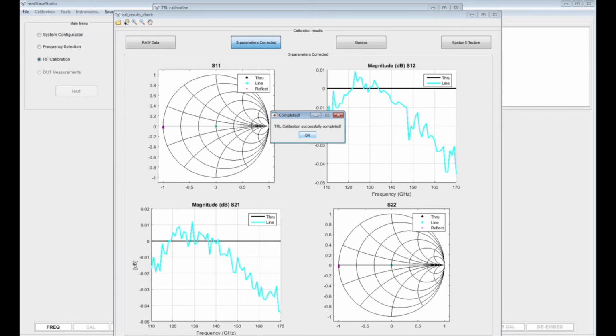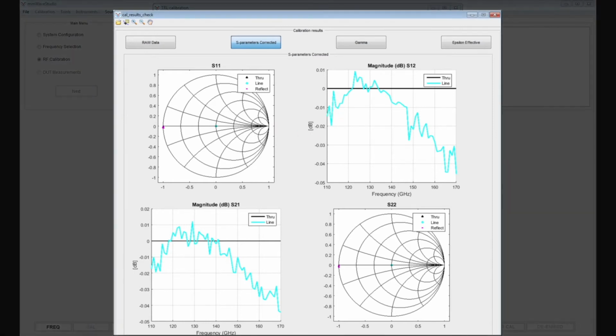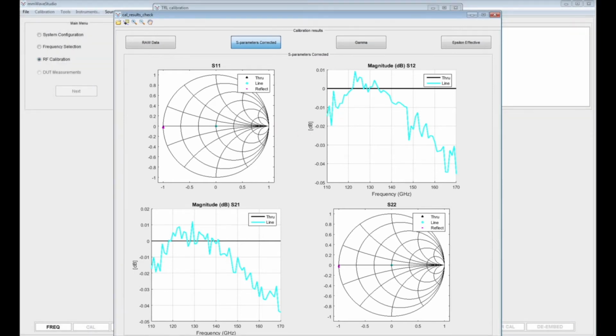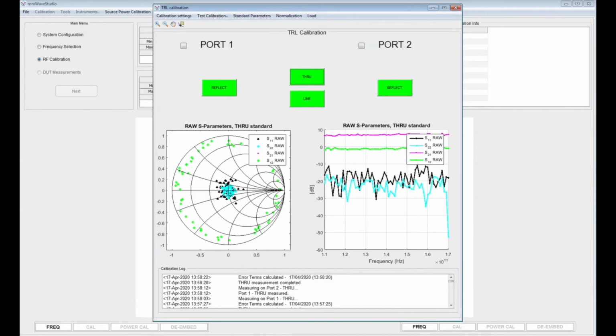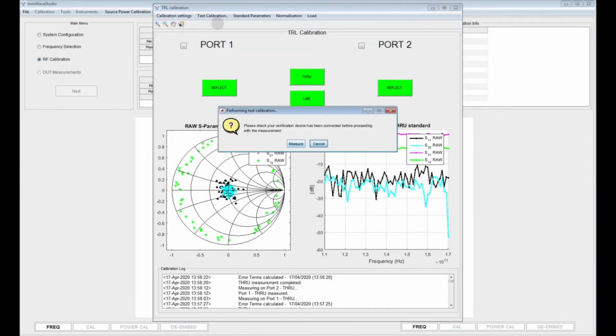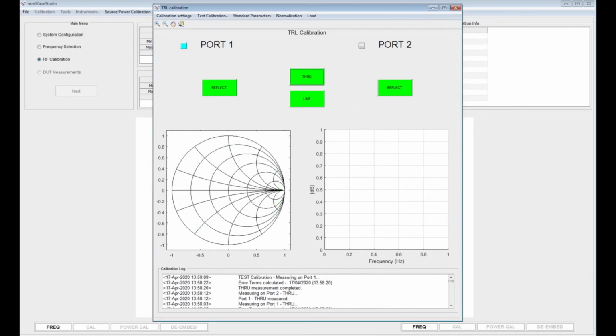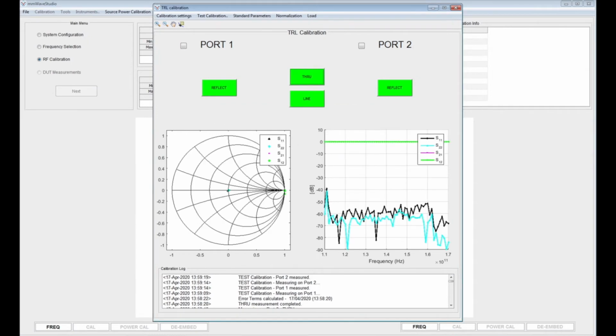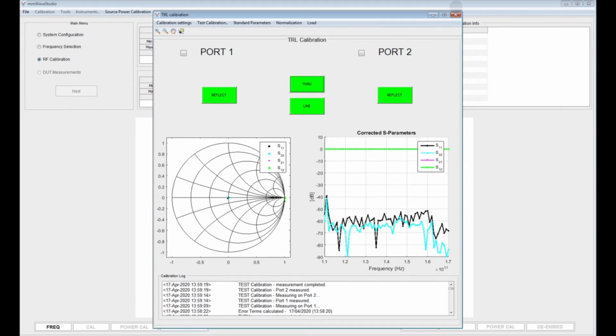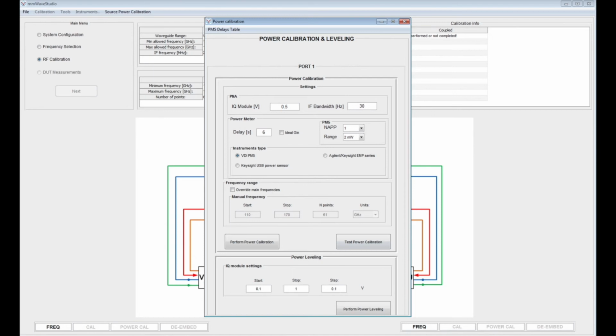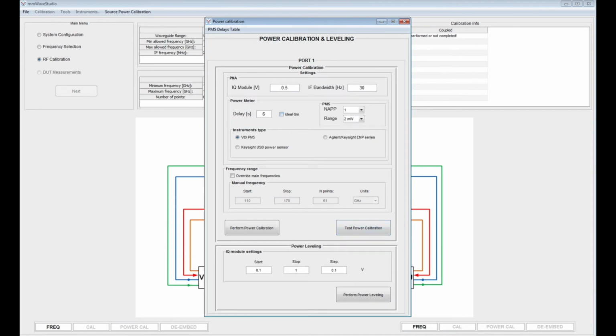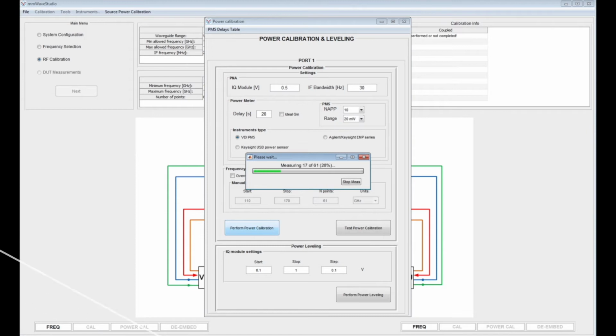When the calibration is done, a calibration results check window pops up where we can inspect the quality of our calibration. Also, we can run a calibration test to see if we are satisfied with our calibration. If the calibration is acceptable, we can move on to the power calibration. For power calibration, we will need to configure the power meter and connect it to the output of the frequency extender on port 1. Then we can click on Perform Power Calibration.